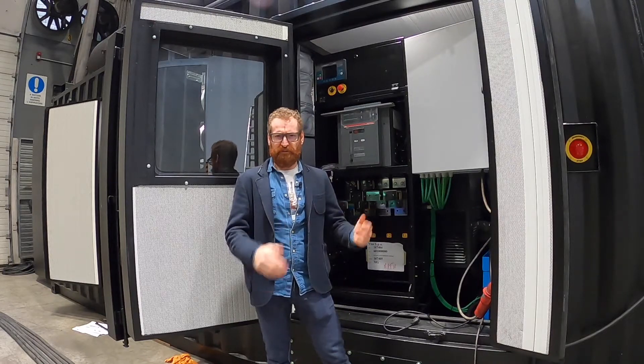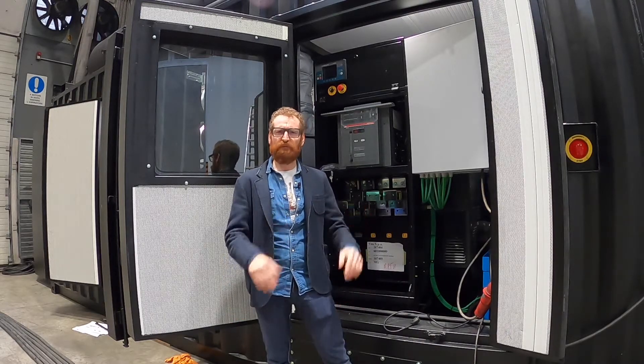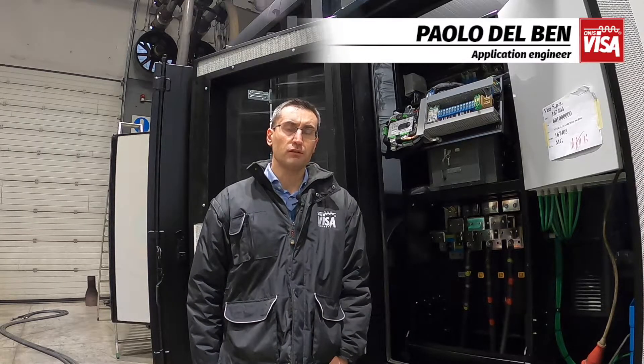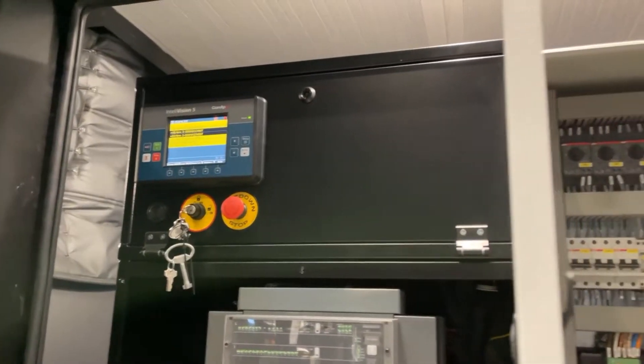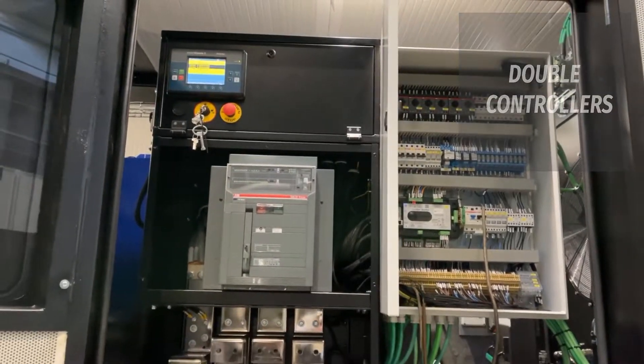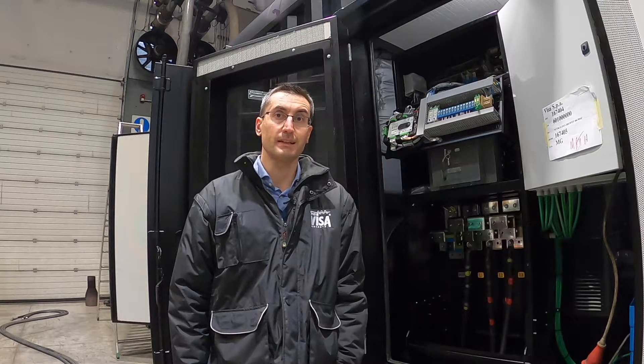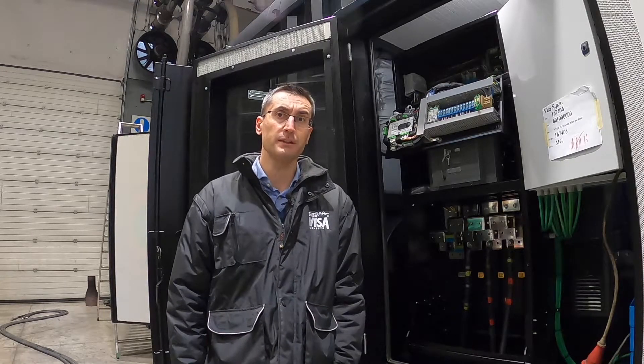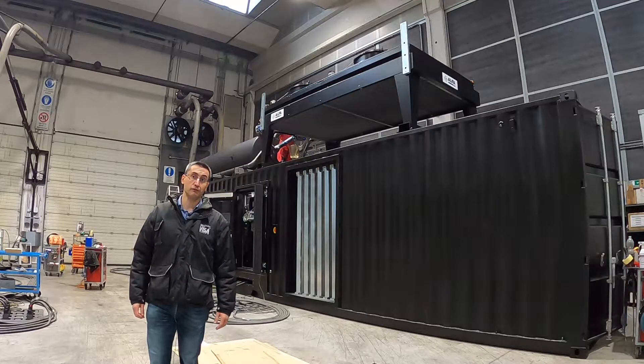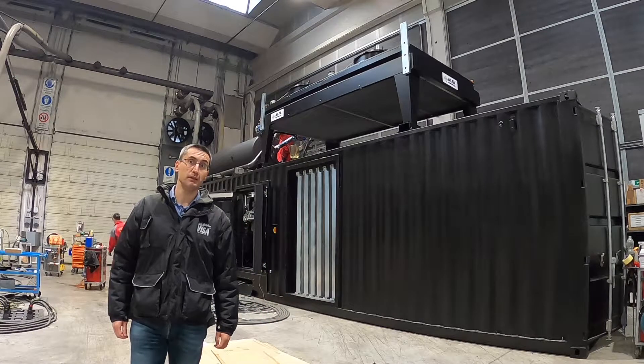Visa also looked after the brain of these two units. A special electrical cabinet was developed to cover any application needs. Let's talk about this electrical aspect with Paolo. Basically, in each genset, the two controllers work simultaneously and share a signal called Heartbeat. In standard operation, the secondary controller is inhibited as long as the primary is up and running. On the other hand, in case of a failure of the primary controller, the secondary controller is able to take full control of the genset in only a fraction of a second. All of this is done automatically without any consequences for the loads. In addition, both controllers can be monitored remotely via Modbus by the customer's building management system.